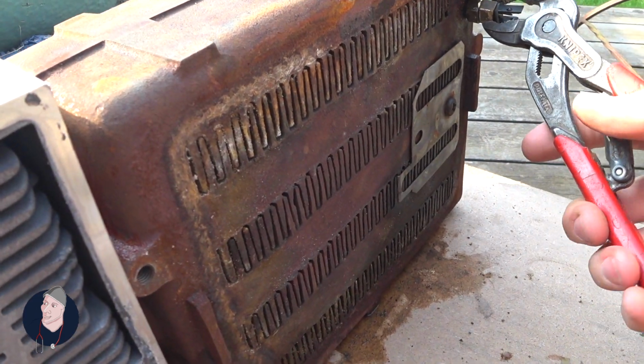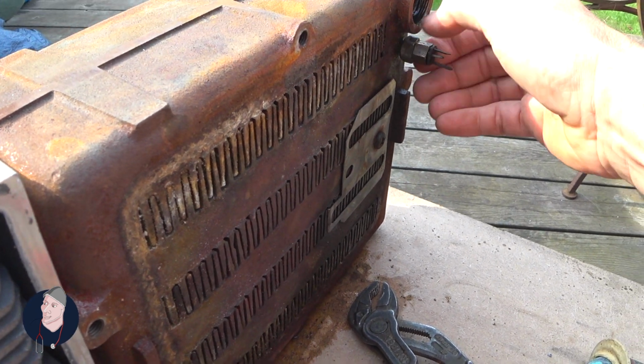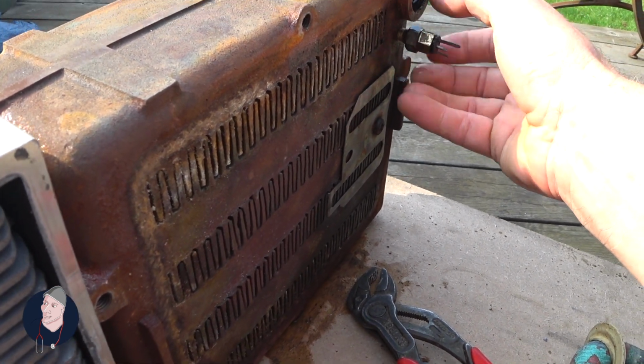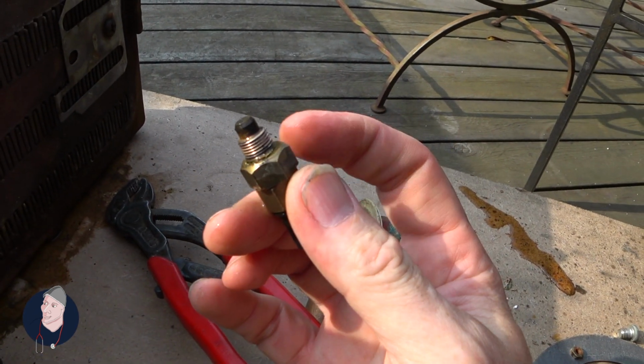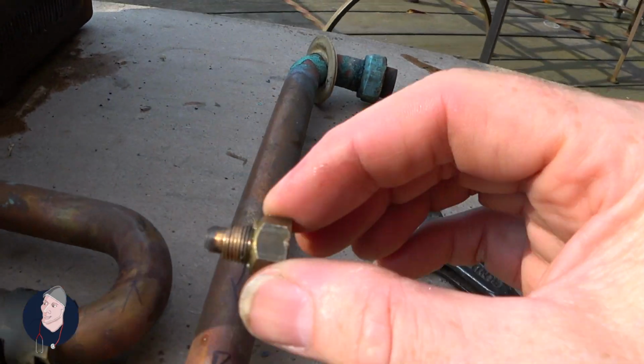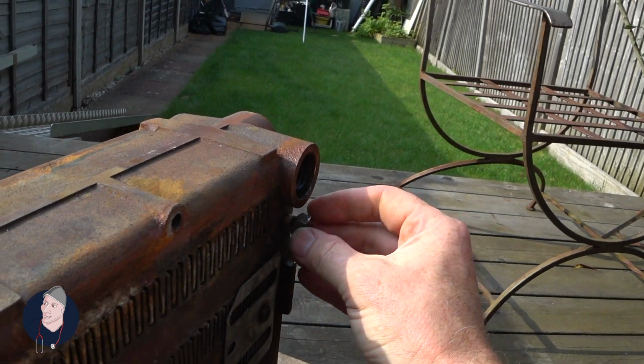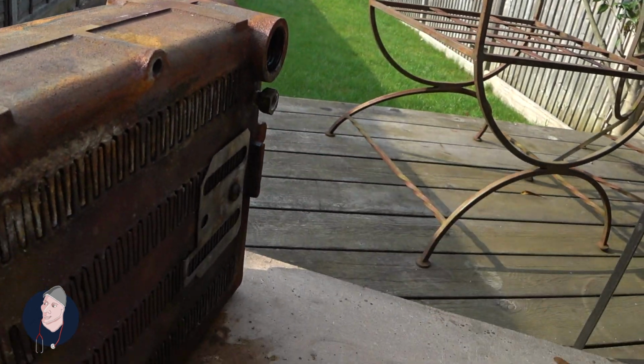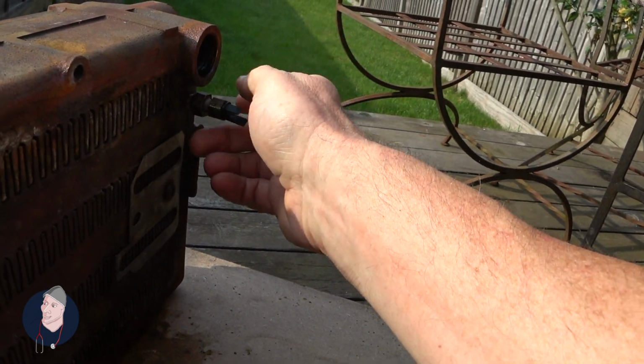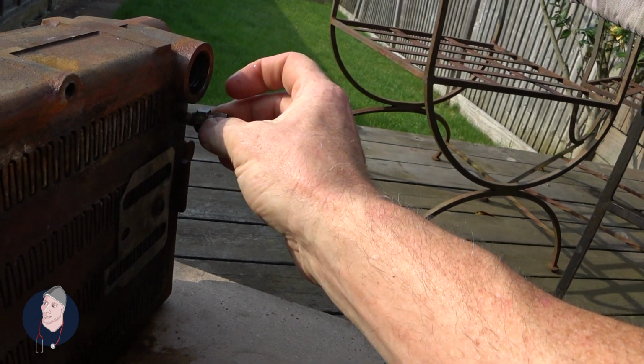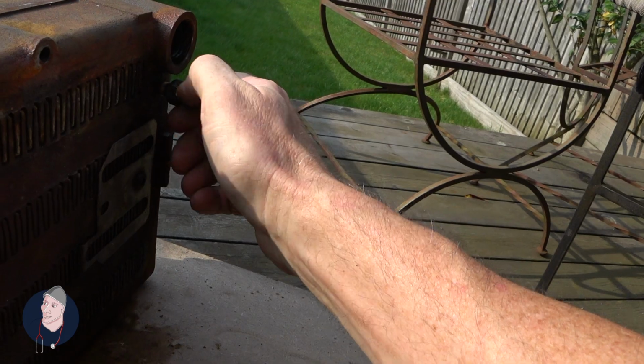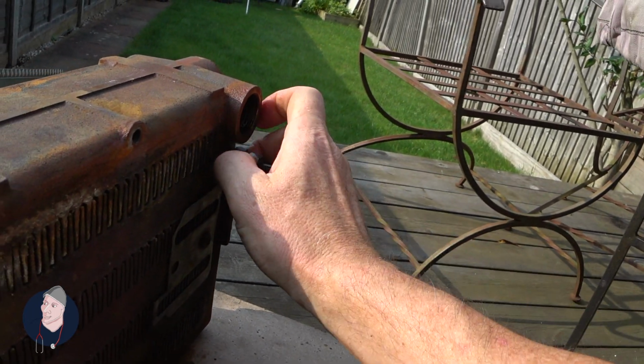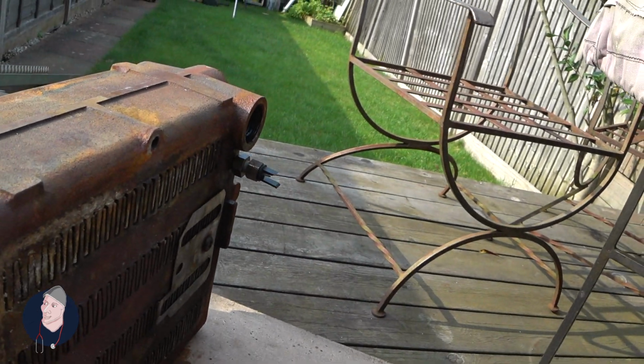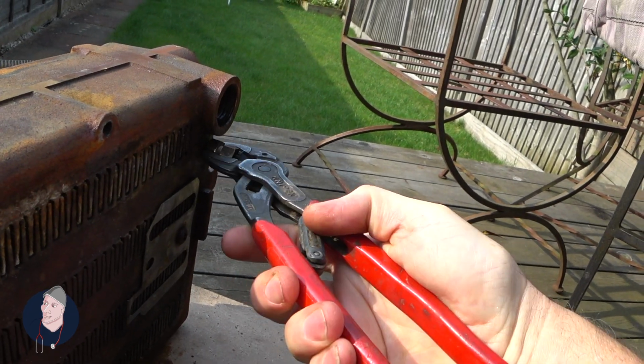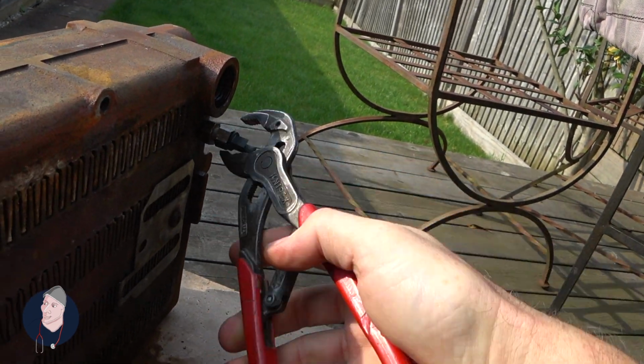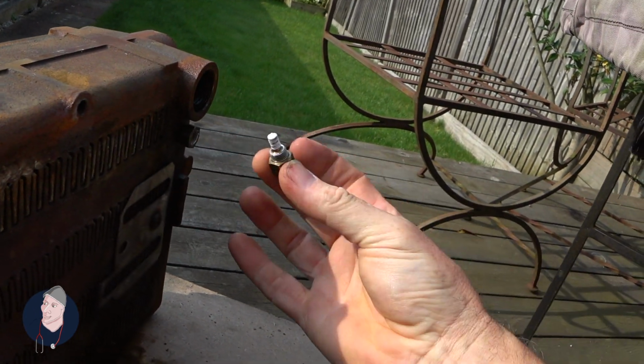That's in essence what it is. So one other thing to note on these, on the flow, on this thermistor here, there are two pockets. So there's the main captive nut, and I'll show you. The main captive nut sits in there and keeps that a dry pocket. Unfortunately, sometimes if you take this out and it takes that secondary bit out, guess what? That is no longer a dry pocket. You're going to get very wet. You must keep that secondary pocket locked into that main heat exchanger. Yeah, so that would stay in, and you would merely undo the second one. That would keep it dry.